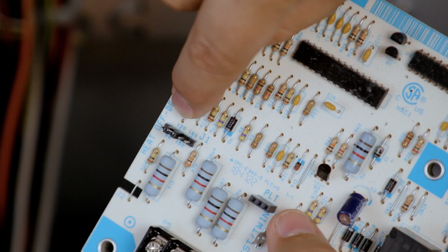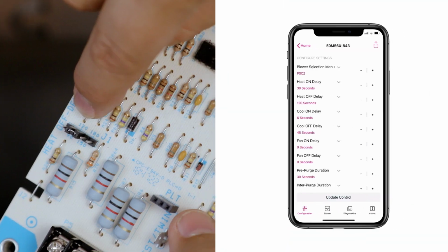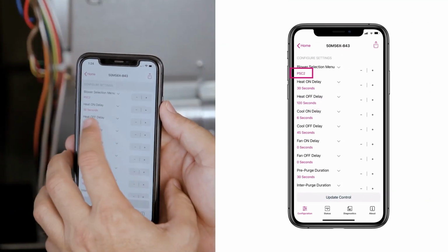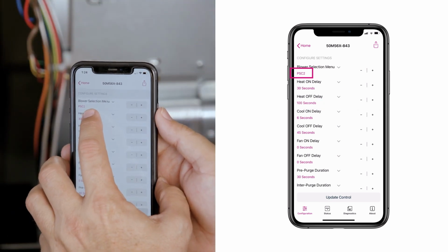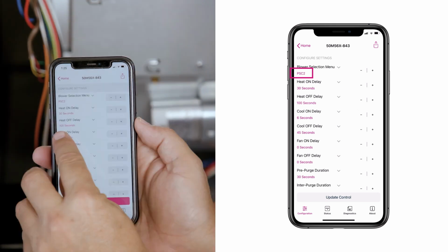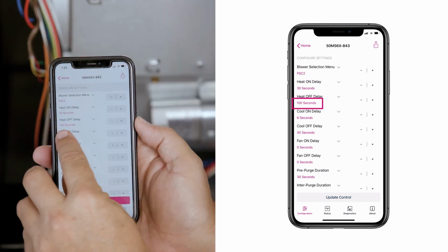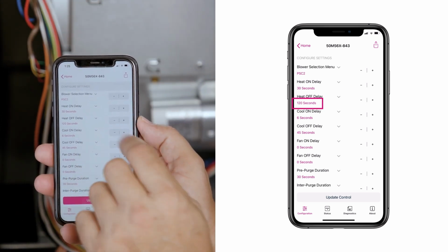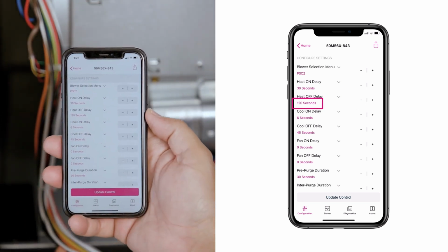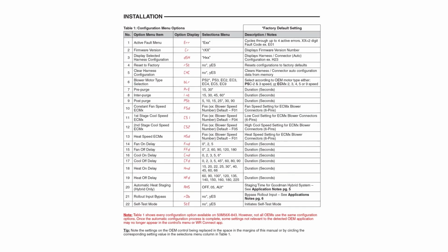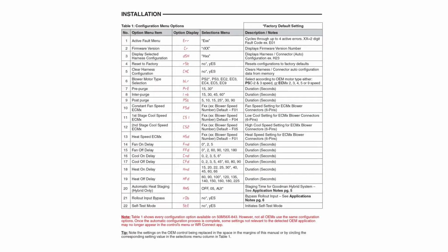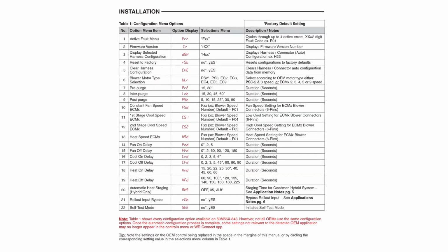The existing control is designed for a 2-speed PSC motor, and the heat-off delay is set at 120 seconds. The 50M56X-843 is factory default set for the blower motor type selection of 2-speed, so no changes needed for this setting. The heat-off delay is factory set at 100 seconds. Change the heat-off setting by tapping plus or minus until 120 appears. Additional configuration options may pertain to your specific application. Reference the instruction manual for a complete list of configuration options.